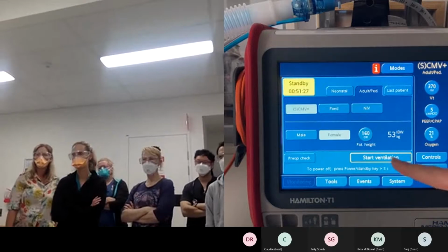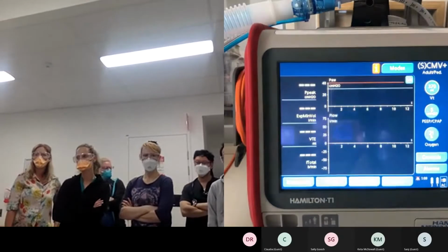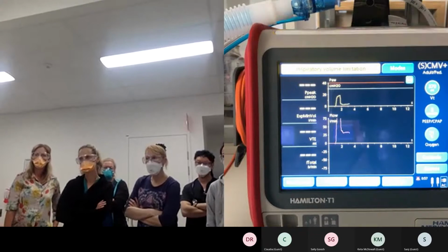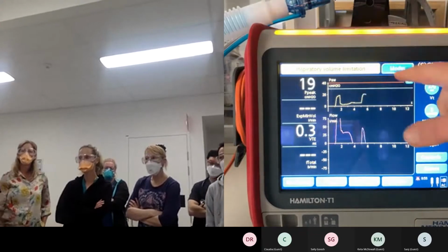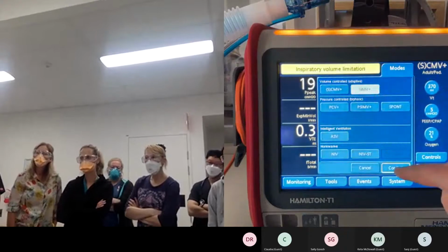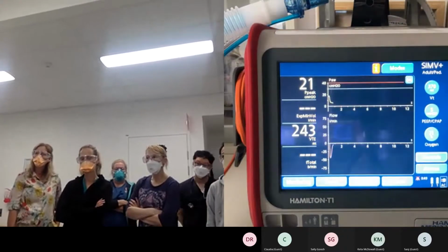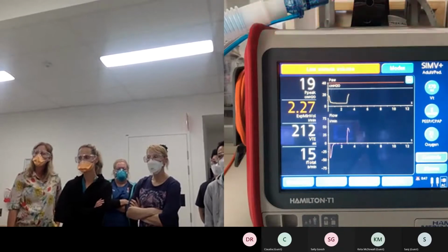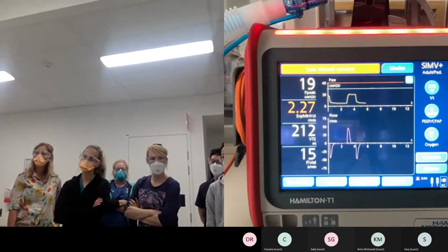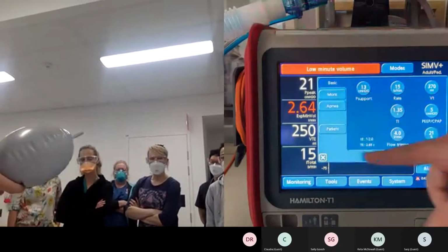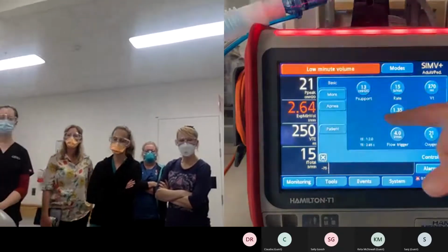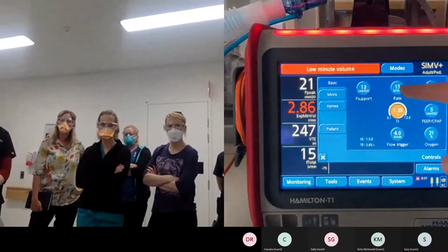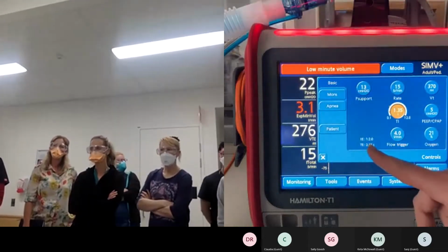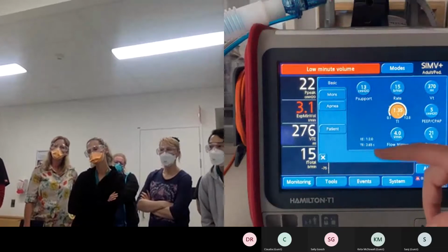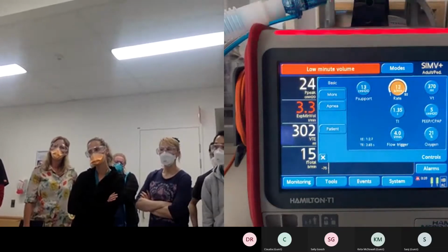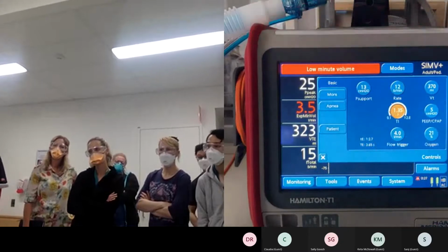Yeah. So once you're ready to go, hit start ventilation. We'll put it on SIMV. You're going to go SIMV, yep. We'll confirm that. And we're just confirming standard settings. We can discuss those a bit more, but we will start ventilation. So we're waiting. Just being aware of the difference between the two: in SIMV, we set a rate and an I time, and down in the bottom corner, we'll have your reflected IE ratio. So you'll see as you adjust your rate, that IE ratio adjusts as well.